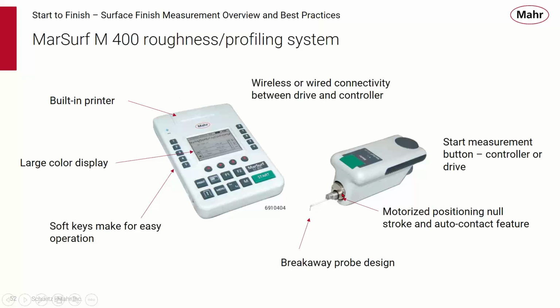And one of the most critical parts of any surface finish gauge is the probe itself. What Mahr does is incorporate two important features. We have a breakaway probe design. The probe is actually held on with magnets so that if it is accidentally bumped or brought too close to the part, the probe will break off, not damaging the system. It can be reapplied and you're ready to go make a measurement again.